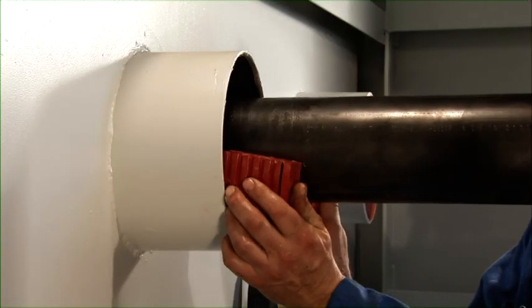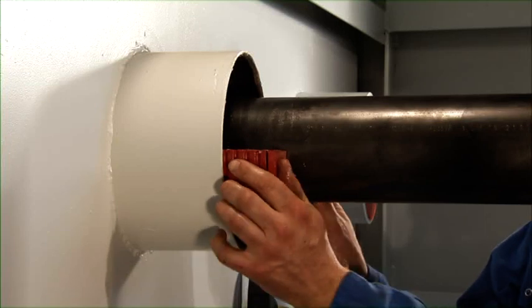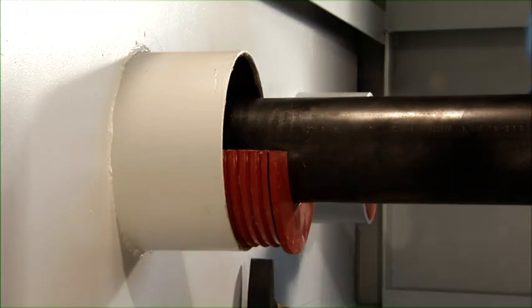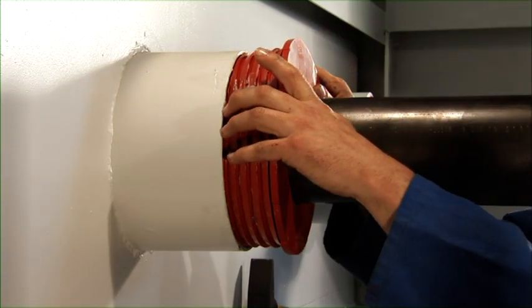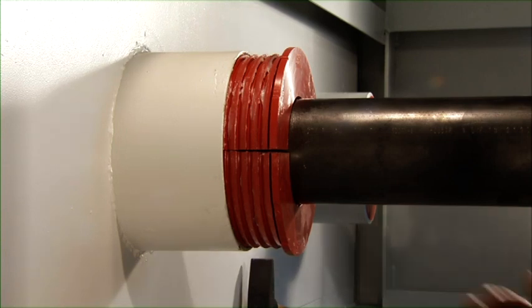The segments of the slip seal plug are placed around the ducted pipe and then pushed into the conduit as far as the first serration. The first serration is smaller than the other serrations to allow positioning of the plug into the conduit.